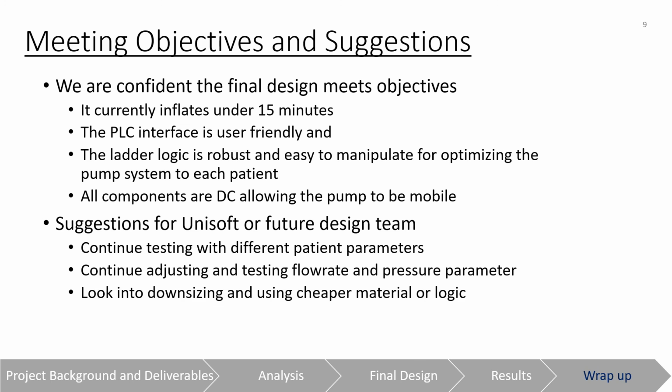In terms of meeting our objectives, we are confident our project was a success. It meets the inflate time requirements, the PLC interface is user-friendly, the ladder logic is robust and optimizable, and all components are DC so the pump can be mobile in the future.